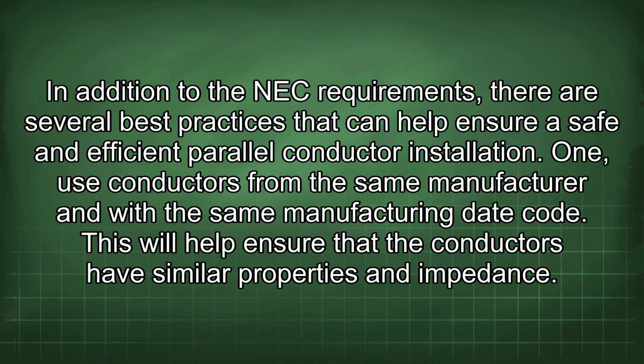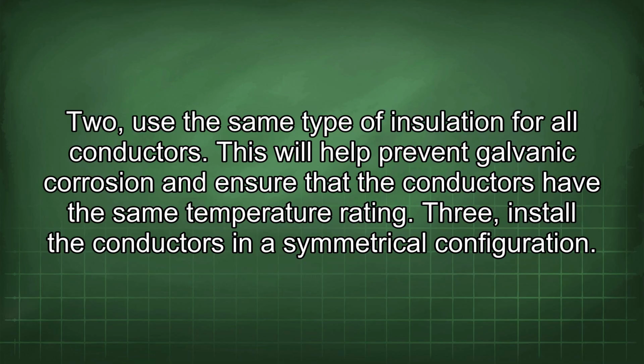In addition to the NEC requirements, there are several best practices that can help ensure a safe and efficient parallel conductor installation. 1. Use conductors from the same manufacturer and with the same manufacturing date code. This will help ensure that the conductors have similar properties and impedance. 2. Use the same type of insulation for all conductors. This will help prevent galvanic corrosion and ensure that the conductors have the same temperature rating.